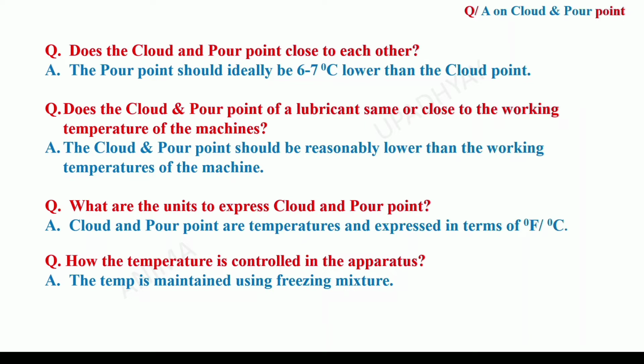Does the cloud and pour point of a lubricant same or close to the working temperature of the machines? The cloud and pour point should be reasonably lower than the working temperatures of the machine to prevent the oil from getting deteriorated as lubricants.